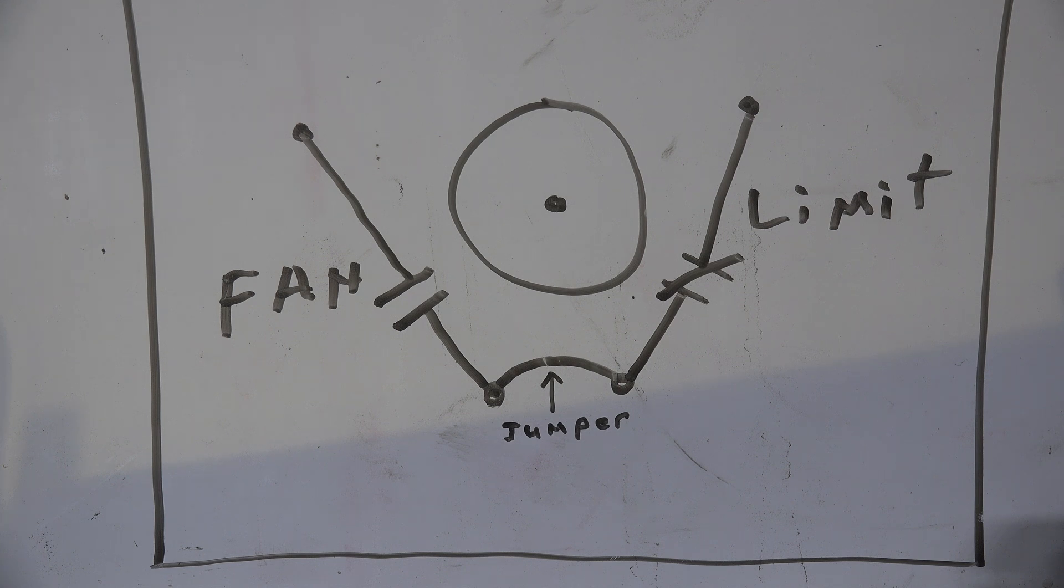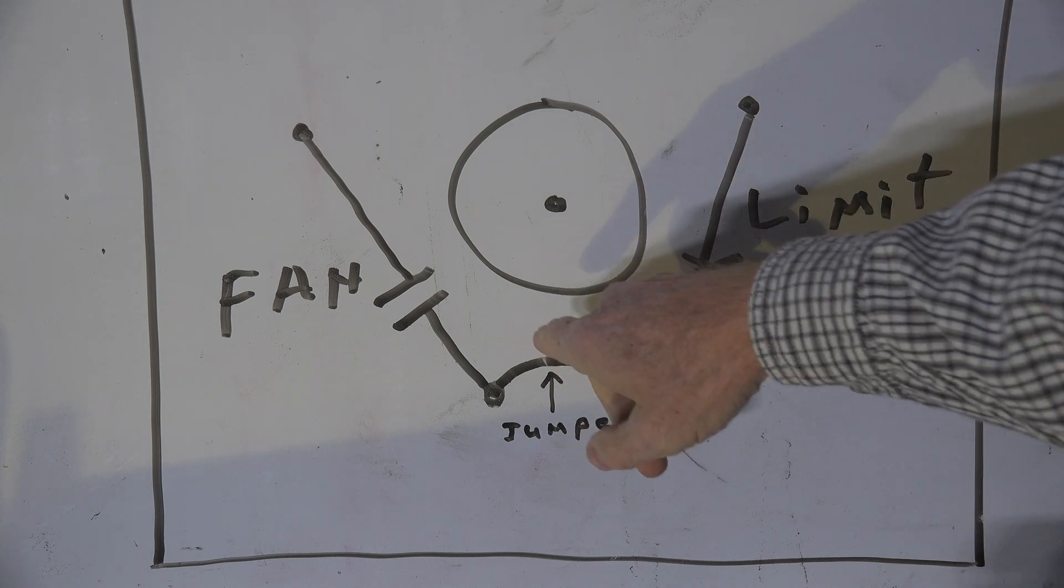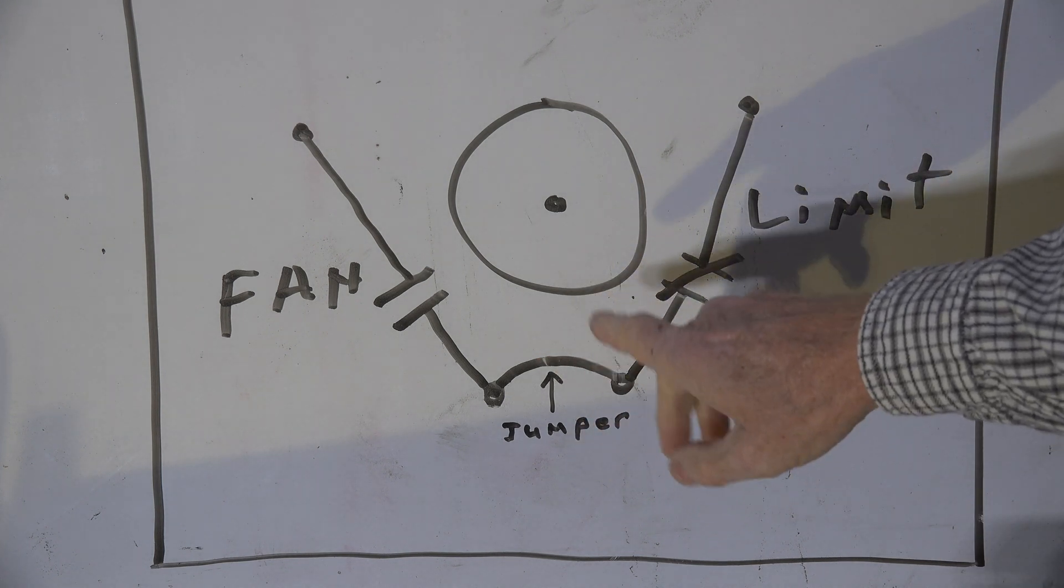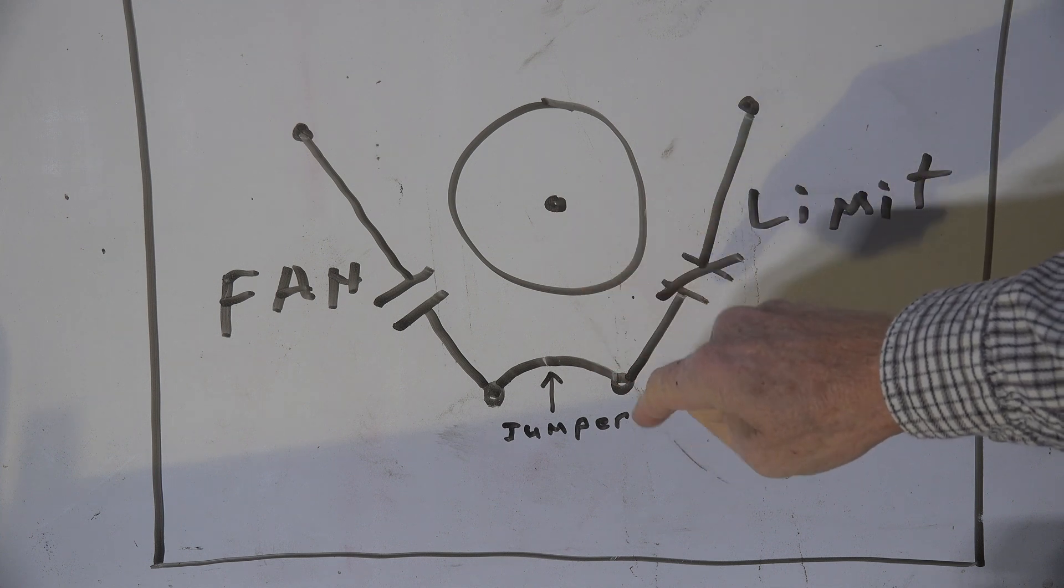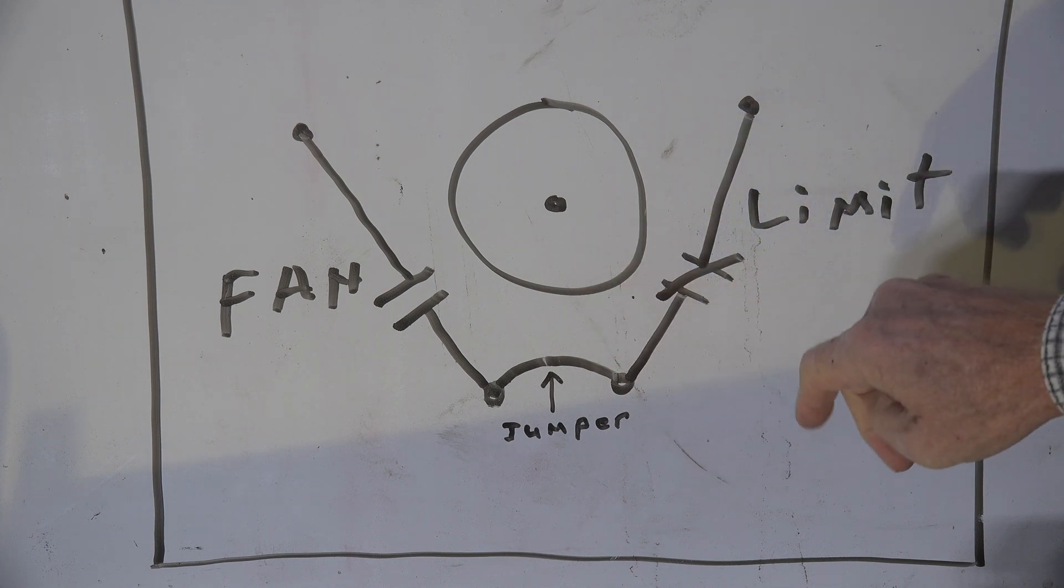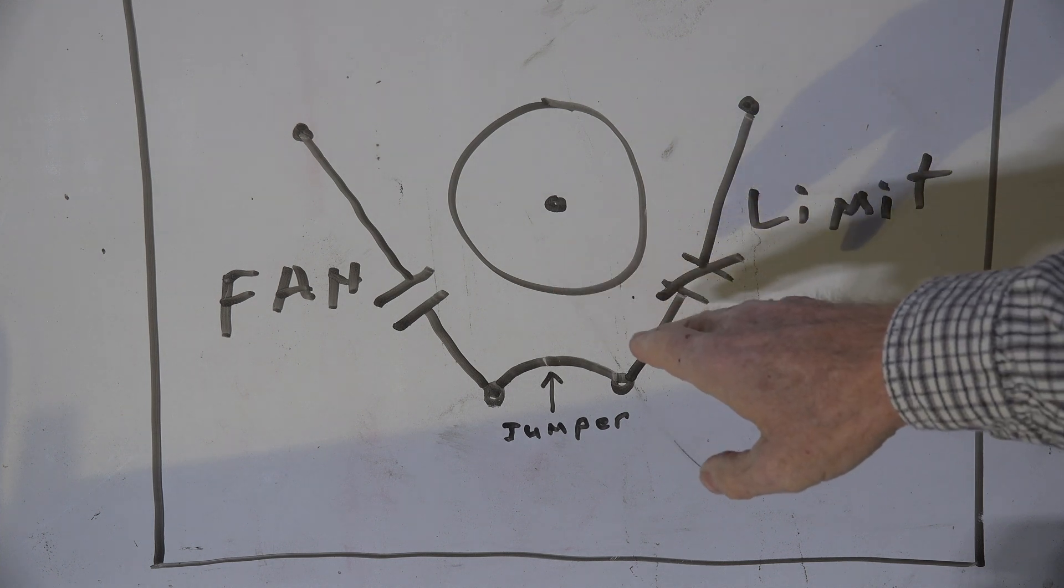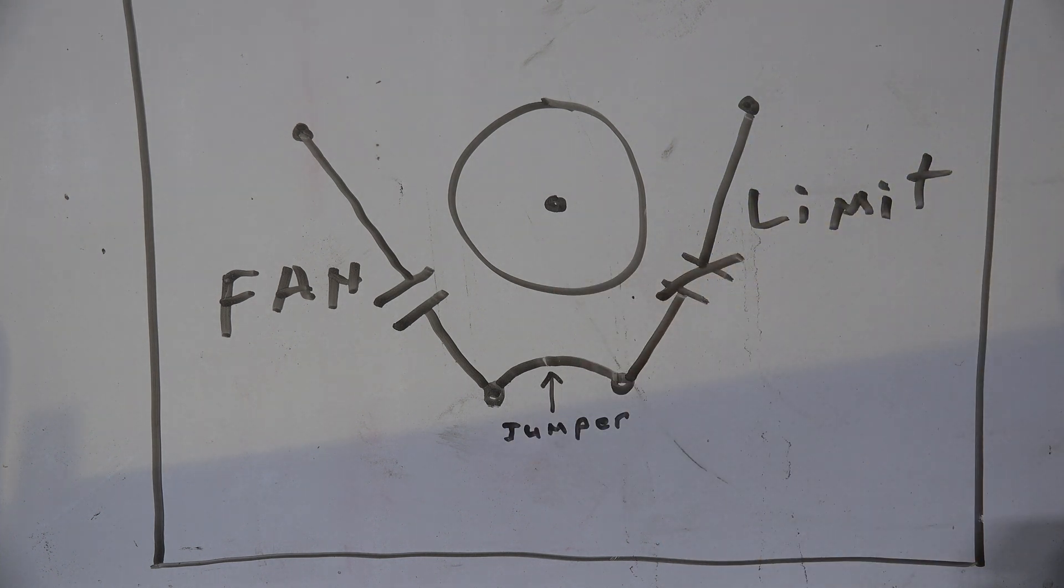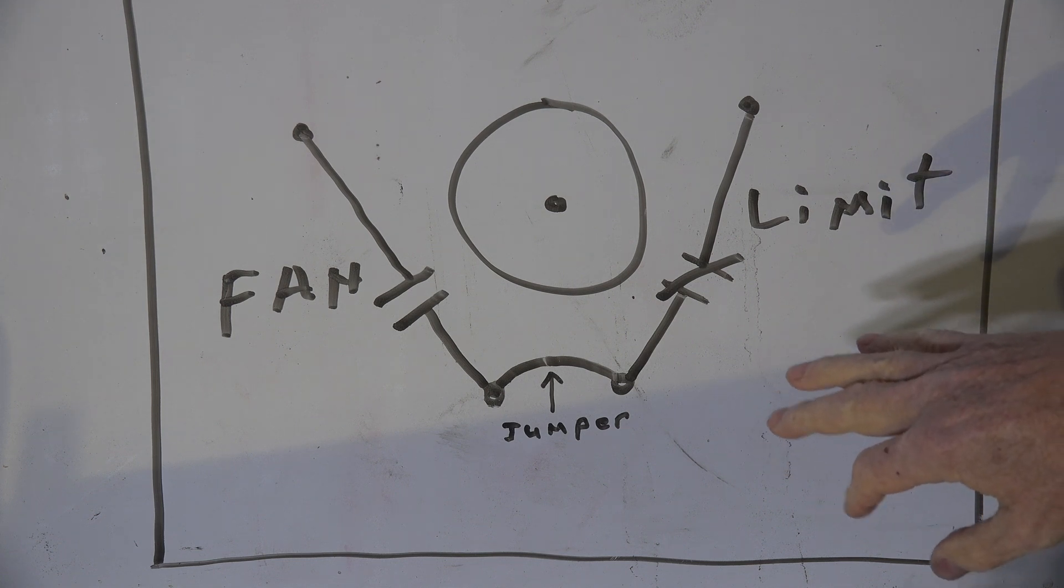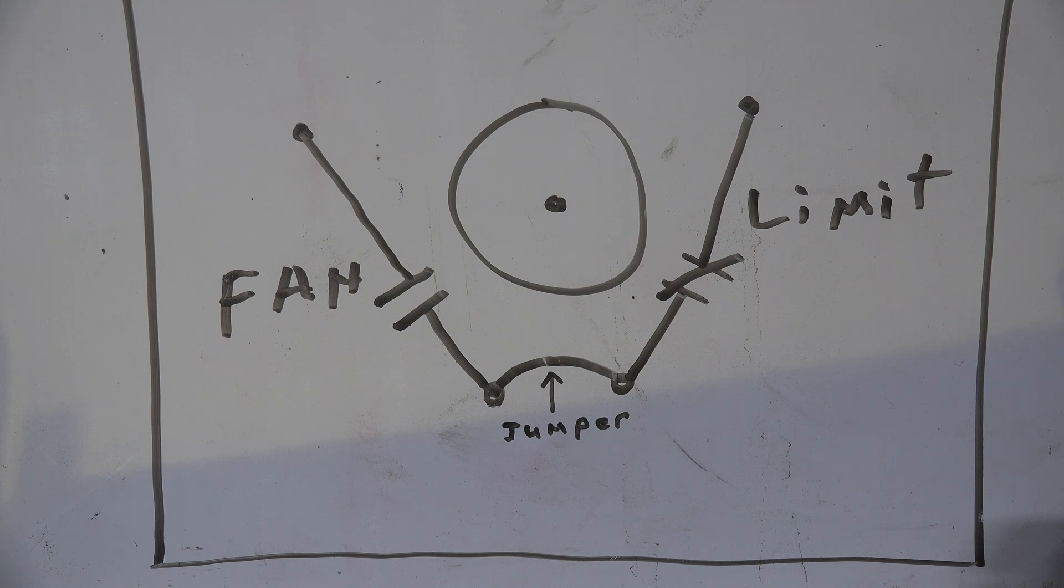The wires—there's two wires that go there—you just take those wires off, isolate them, because they're 24-volt wires. You isolate them and abandon that part of the switch because the newer switches just don't have that. It's a fairly simple switch once you understand the diagram that's on it, so you should be able to wire the thing up properly and make it work. That's it on this one.